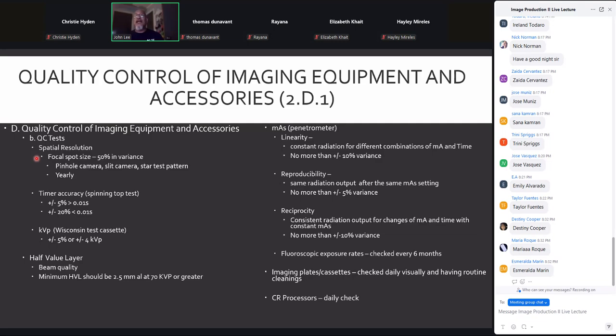mAs can be checked for linearity, reproducibility, and reciprocity. Linearity: consistent radiation for different combinations of mA and time, where we have no more than 10% variance. So if we set an mA and set a time and then make an exposure and then double the time or double the mA or half the mA, that should be consistent with a decrease by a factor of 2 in exposure. That's what linearity checks.